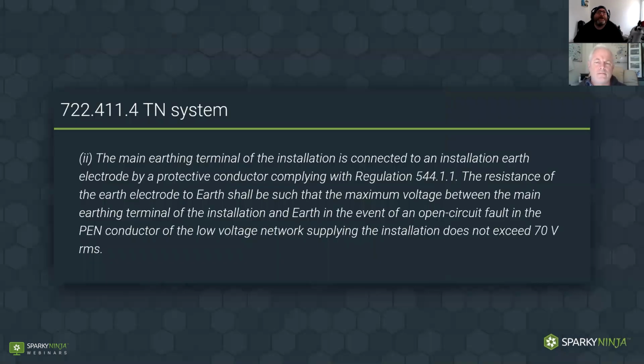The next situation, and this is all in the 18th edition, is where the main earthing terminal of the installation is connected to the installation's earth electrode by a protective conductor complying with 544.1.1. That, I believe, is the regulation for the sizing of the main bonding on PME or non-PME. If you go to the beginning of the bonding sizing section, it's sized to that.